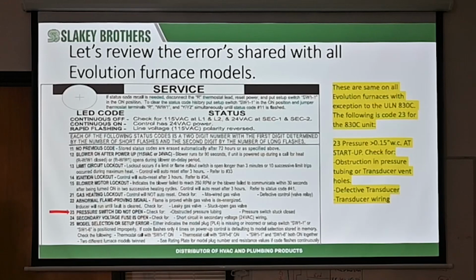You check the resistance and everything looks okay, and your furnace board is still giving you a 25, and you've got these switches off, then something's wrong with that board. You just have to replace the board. Usually, 99% of the time, the 25 is because we forgot to put the little model chip back in there.